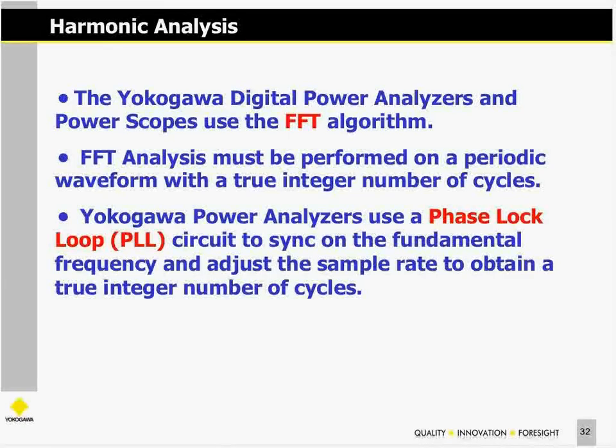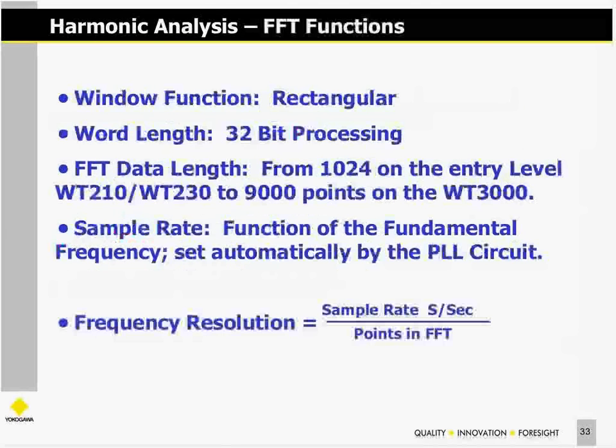Now, if you remember FFTs, FFT analysis must be performed on periodic waveforms with a true integer number of cycles. And what we do in our power analyzers is that we use a phase lock loop tuning circuit. We're actually using that PLL circuit to find the fundamental frequency of the waveform, and then we adjust the sample rate to obtain a true integer number of cycles to calculate our FFT. So let's see what all that means.